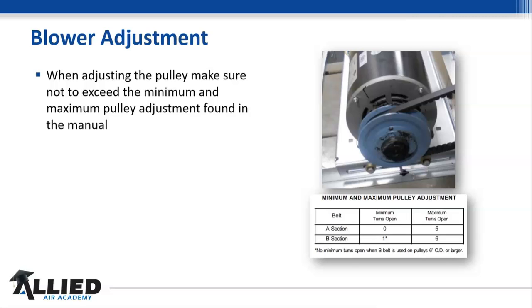And it helps the guys out in tech service, and it speeds them up because they can look up a bill of material, see exactly what kit went in there and what size pulleys is in there. So if you need to go larger or smaller, we don't always recommend that because you have to watch out for wire sizes if you change motors and things of that nature. So getting the kit the closest to what you need is always imperative, but there's always going to be some changes out there.